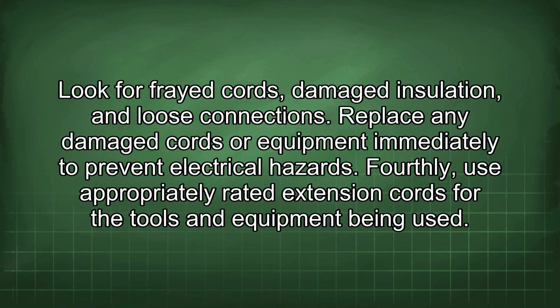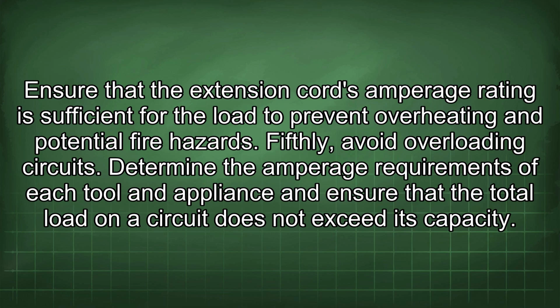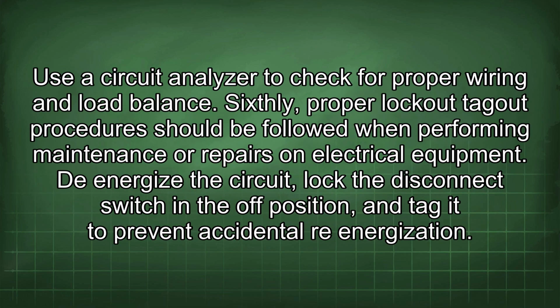Fourthly, use appropriately rated extension cords for the tools and equipment being used. Ensure that the extension cord's amperage rating is sufficient for the load to prevent overheating and potential fire hazards. Fifthly, avoid overloading circuits. Determine the amperage requirements of each tool and appliance and ensure that the total load on a circuit does not exceed its capacity. Use a circuit analyzer to check for proper wiring and load balance.